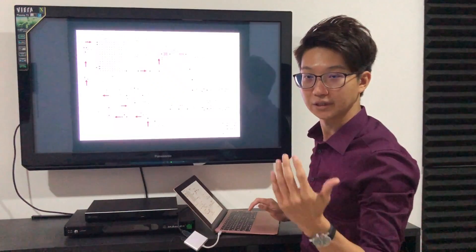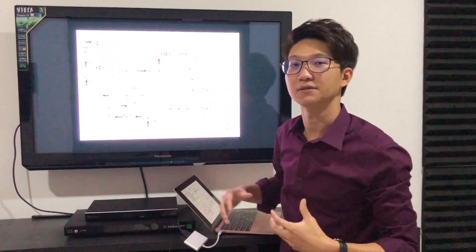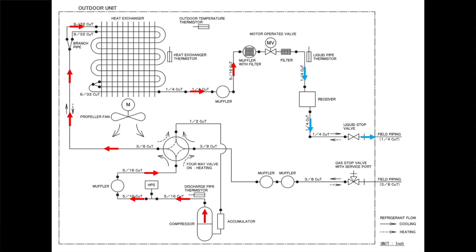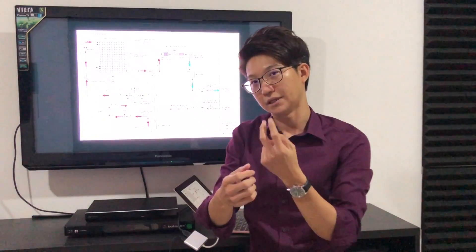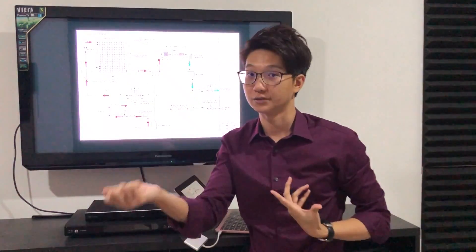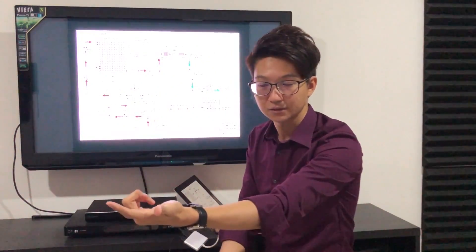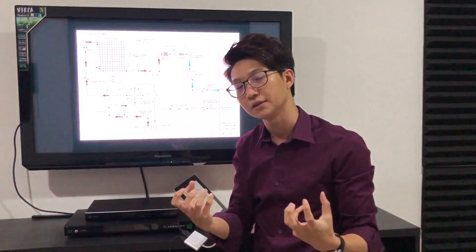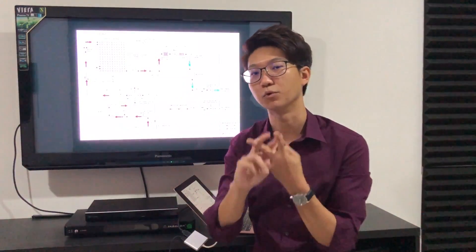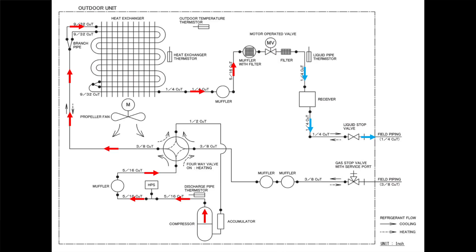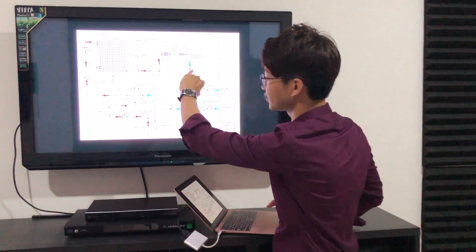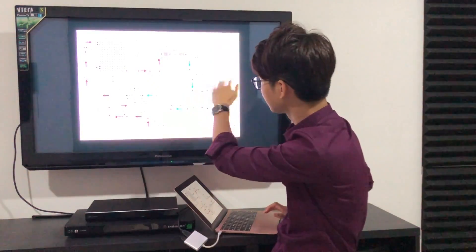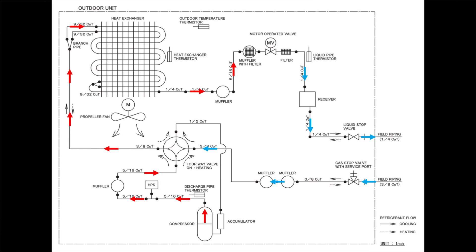After condensing back to liquid, the refrigerant goes through the expansion process — since the new air conditioner has the expansion valve inside the outdoor unit — and the cold refrigerant is then sent to the indoor unit. That's why both refrigerant tubes now need to be insulated: one going to the indoor unit carrying cold liquid-gas mixture, one coming back already fully evaporated as gas. Everything returns as gas and goes back to the compressor.